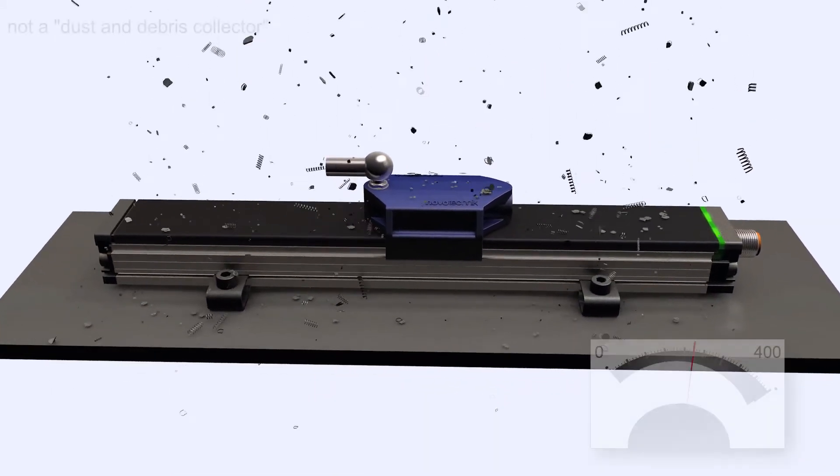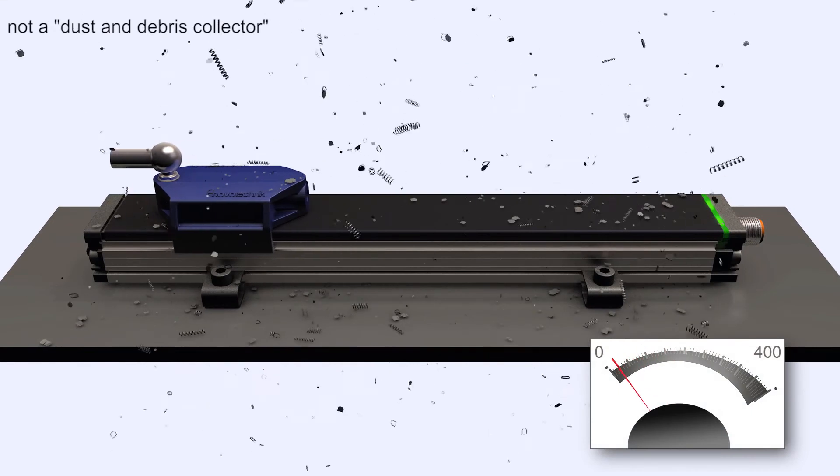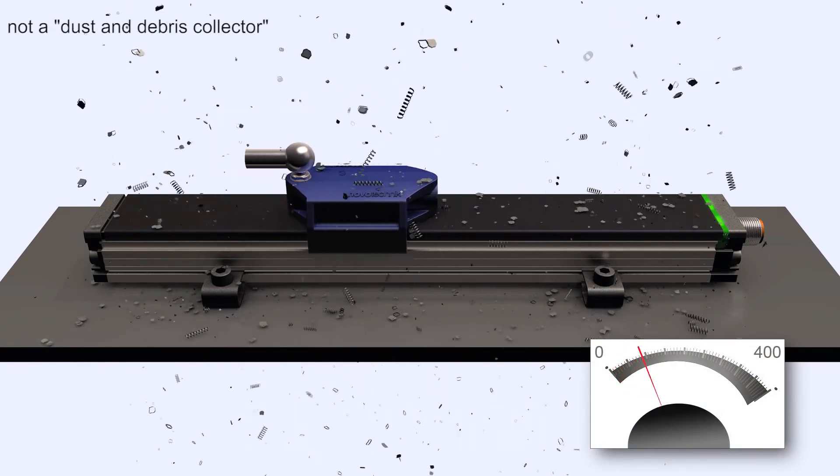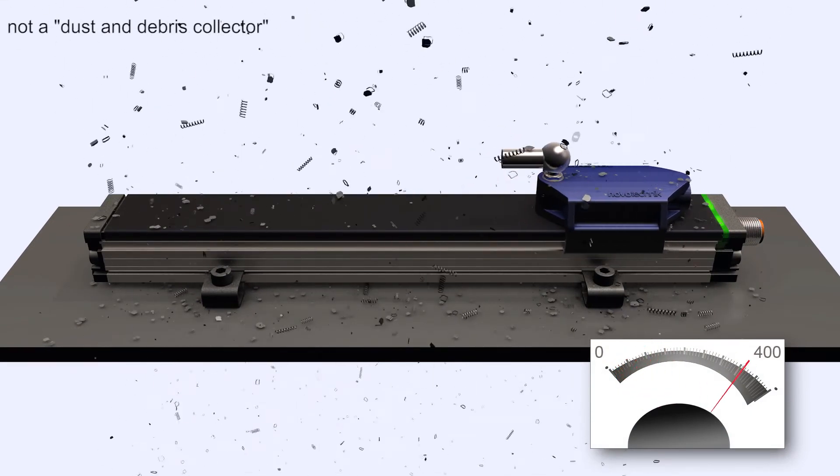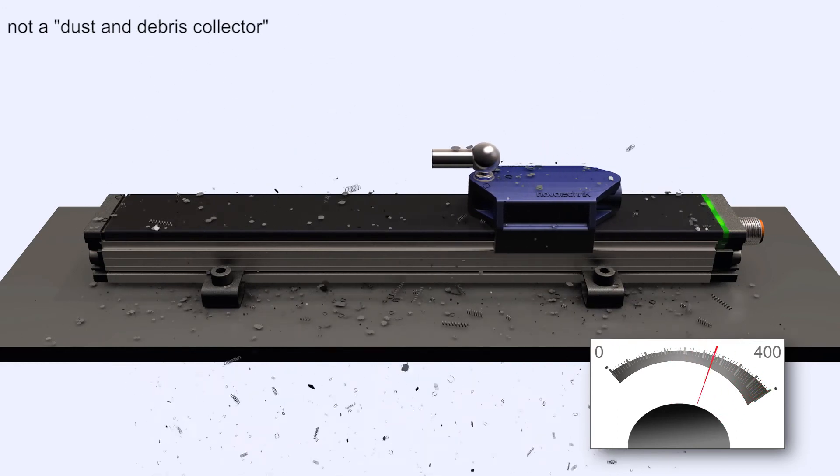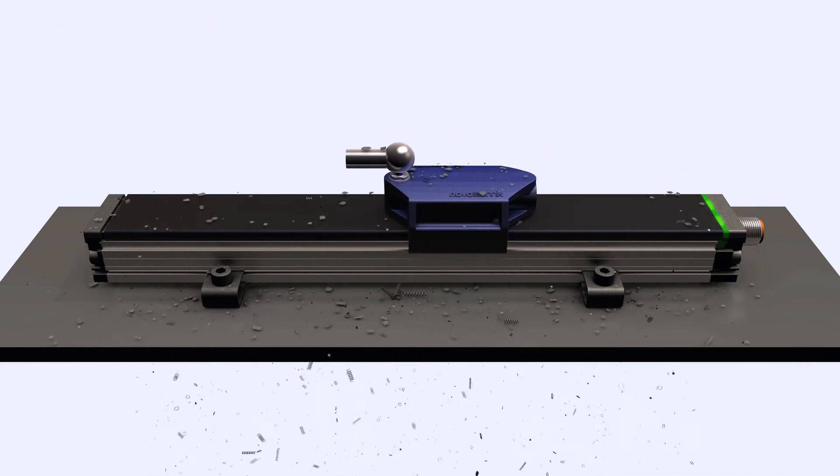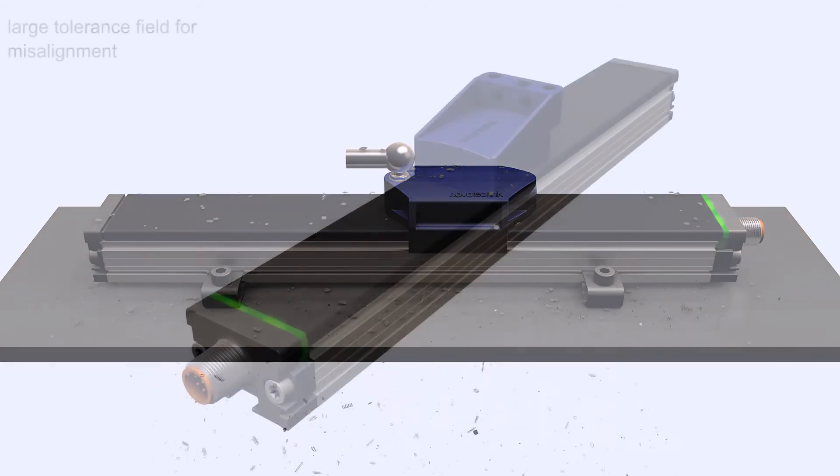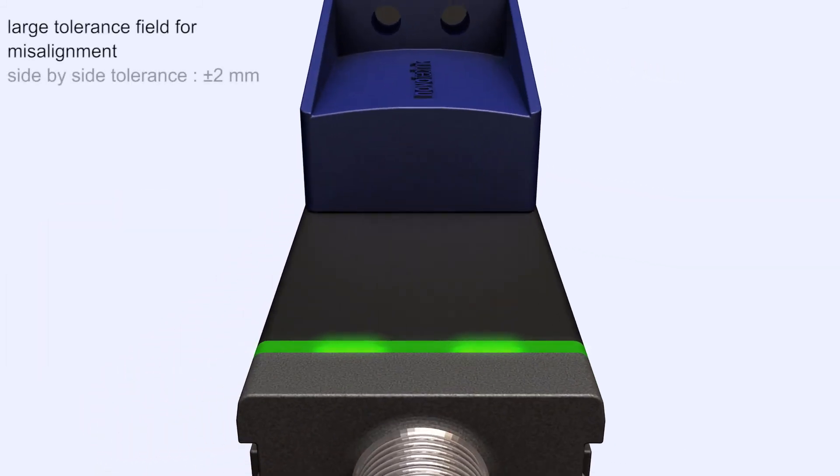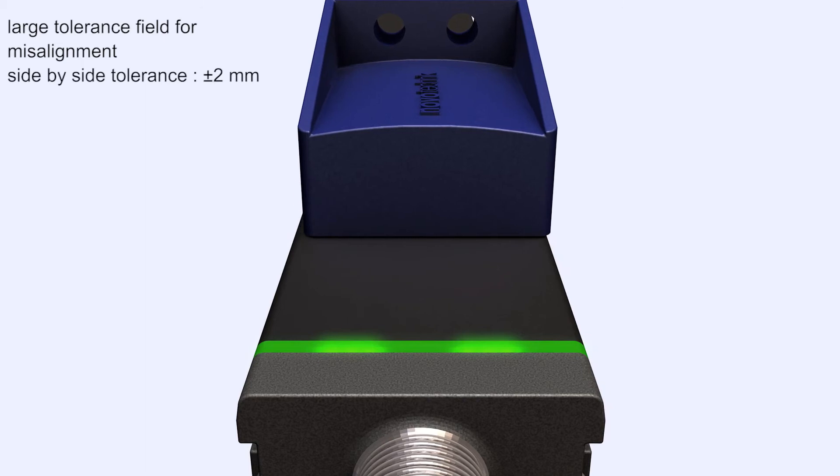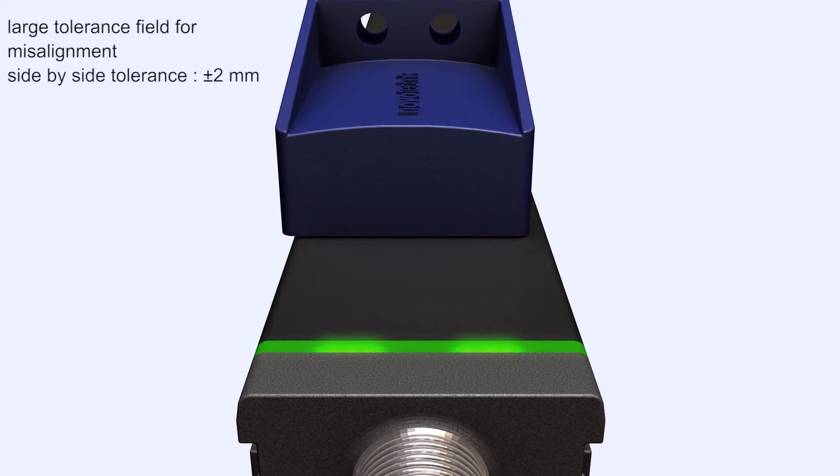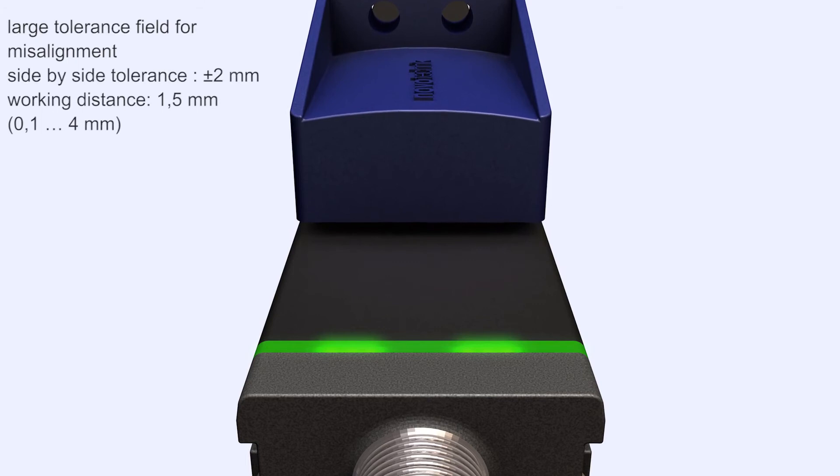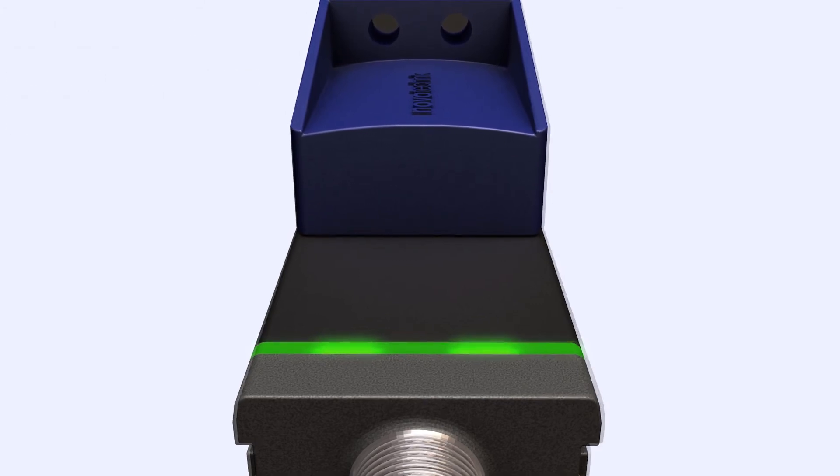Since the position marker is not magnetic, no magnetic debris will collect on it. The output signal remains stable and the mechanical function is not impaired. The sensor tolerates a side-to-side misalignment of 2 millimeters. The working distance between sensor and position marker is wide, with a range of 0.1 to 4 millimeters.